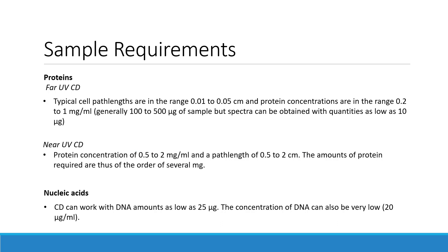Regarding sample requirements for circular dichroism assays, if you want to obtain CD spectra of proteins in the far UV region, typical cell path lengths are in the range of 0.01 to 0.05 cm and protein concentrations are in the range of 0.2 to 1 mg per milliliter, generally 100 to 500 micrograms of sample, but spectra can be obtained with quantities as low as 10 micrograms. In the near UV region, protein concentrations of 0.5 to 2 mg per milliliter are needed with a path length of 0.5 to 2 cm, and the amounts of protein required are thus of the order of several mg. For nucleic acids, CD can work with DNA amounts as low as 25 micrograms, and the concentration of DNA can be as low as 20 micrograms per milliliter.